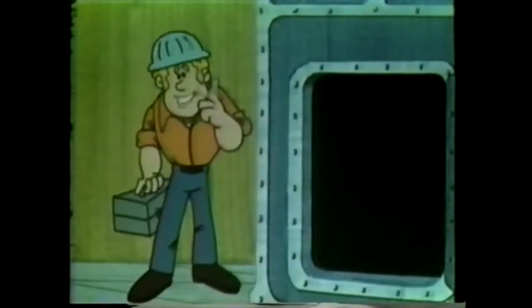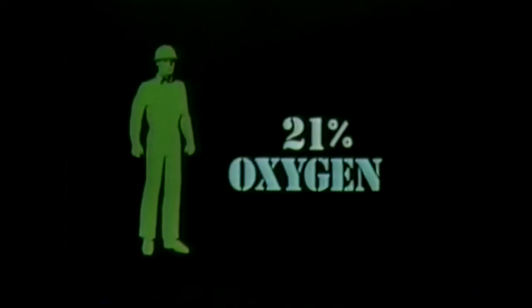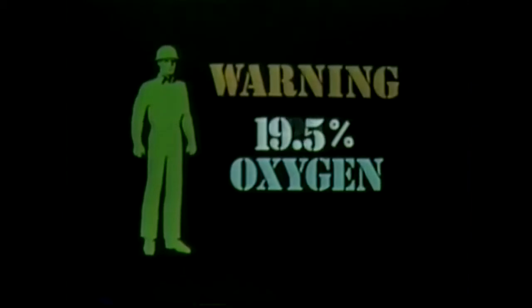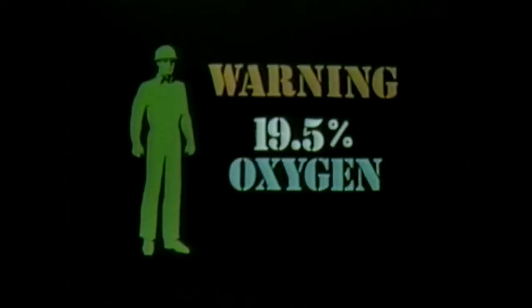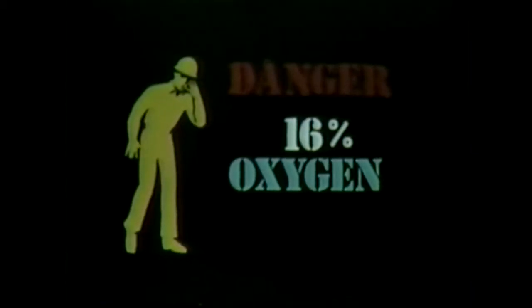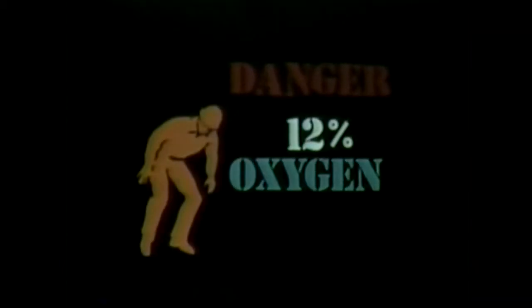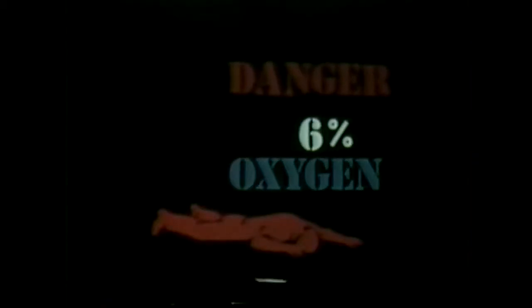Yeah, but you mean a few percent less oxygen can actually make a difference? Usually it doesn't happen gradually. But if we lower the oxygen to only 19.5%, just that much less is the minimum required by law to sustain normal life. And as the percent of oxygen decreases, it rapidly gets dangerous. Dizziness, a more rapid heartbeat, a buzzing in your ears, maybe a headache. Muscular control becomes difficult. Permanent brain damage can occur. Then paralysis, unconsciousness, death in 5 to 8 minutes.